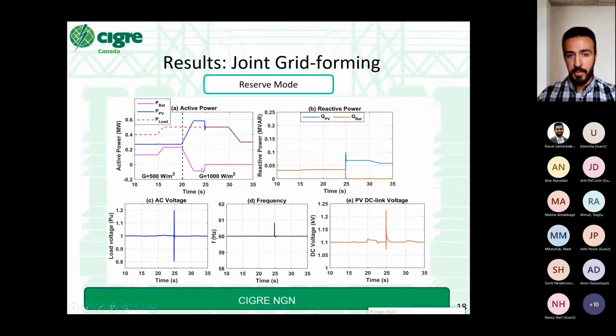Prior to the battery energy storage trip, we can see from the reactive power that the PV and the battery are sharing the reactive power burden. As the battery trips, the PV takes over and starts providing the required reactive power. The AC voltage, frequency, and the DC link voltage of the PV also show a stable response.